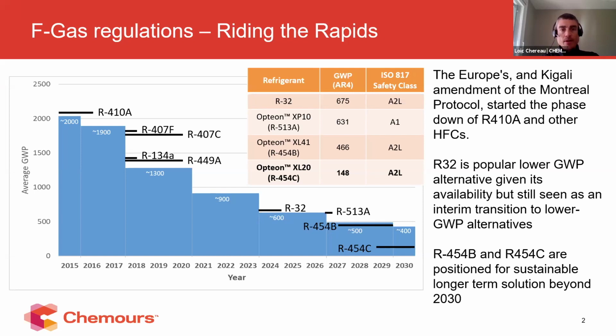Coming from the 410A refrigerant or from the 407C refrigerant, which is also used in the heat pump industry, as you can see, there is a step down on the CO2 quota, which is permitted by the current F-gas regulation in Europe. Different from the commercial refrigeration industry, where there are already some bans on new equipment using a very high GWP refrigerant like R404A, in the heat pump industry there is no ban yet, but anyway we are following the same step down on the CO2 quota to reduce the average GWP of the refrigerant that can be used in the heat pump industry.